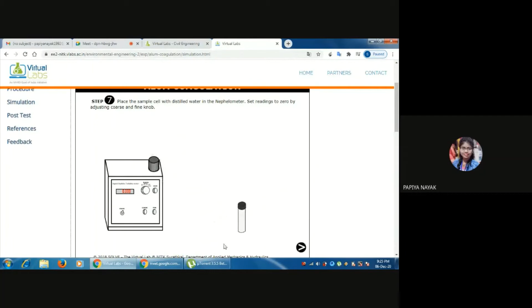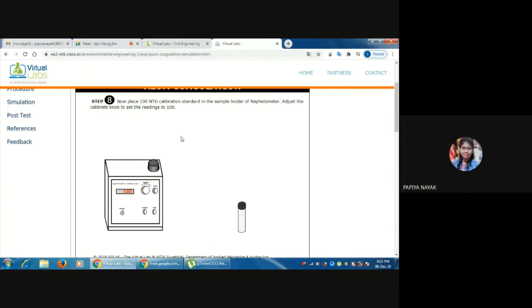Now place the 100 NTU calibration standard in the sample holder of the nephelometer and adjust the calibrate knob to set the reading to 100. So this is the nephelometer tube which is filled with the 100 NTU calibration standard. NTU means nephelometric turbidity unit. First we place this nephelometer tube in the nephelometer. Yeah, the value is 97.00. Now we adjust the calibrate knob to set the reading to 100. Now we have set the value at 100. So the apparatus is set at 0 and 100.